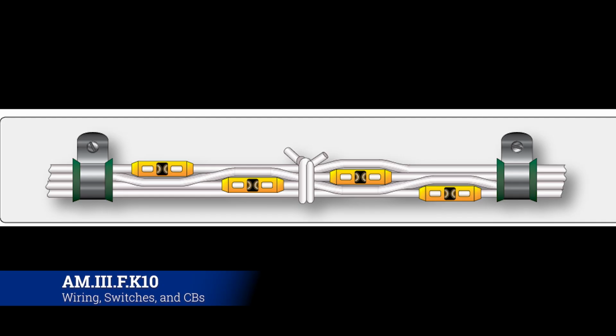The best way to do it is to take what we'll call bundle A and bundle B. Bundle A is going to lay into bundle B. You take the longest wire from bundle A, lay it into bundle B, cut bundle B's wire wherever that bundle A wire lands, and splice right there. Then you take the next wire from bundle A, trim off 2 or 3 inches, lay it over into bundle B, and repeat the process. As you keep doing that, it will stagger the splices out.